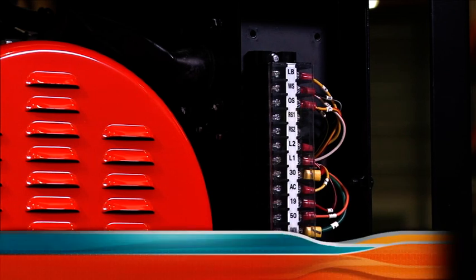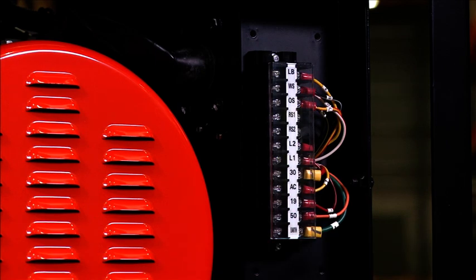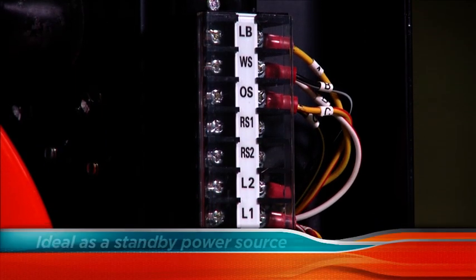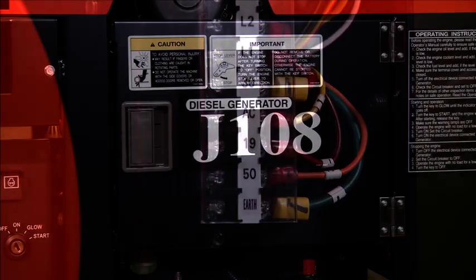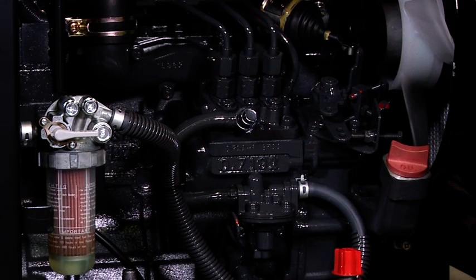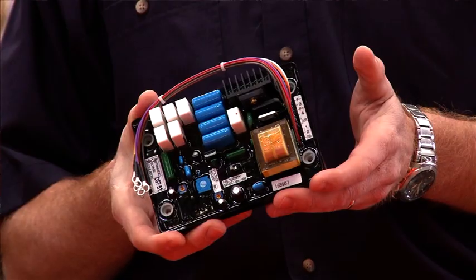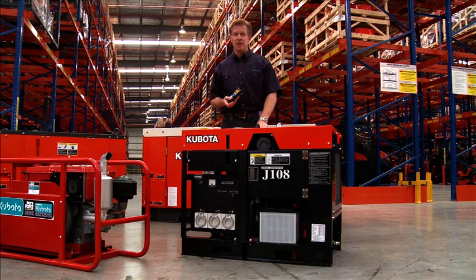Access terminals are provided for use with optional automatic mains failure panels that allow for automatic operation in the event of a grid power failure. This will save you hundreds if your intention is to use this machine as a standby power source. Checking oil and water levels and access to filters is all on one side of the unit, allowing for ease of maintenance. The J-Series also have a transistor type automatic voltage regulator to ensure a stable power supply, and these units will also automatically shut down in the event of oil pressure loss or increased temperatures.